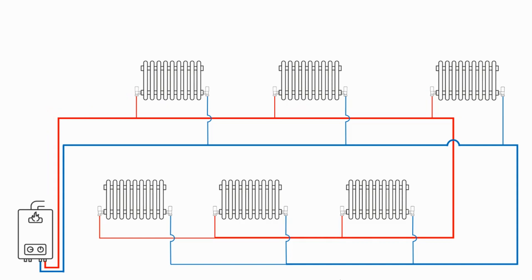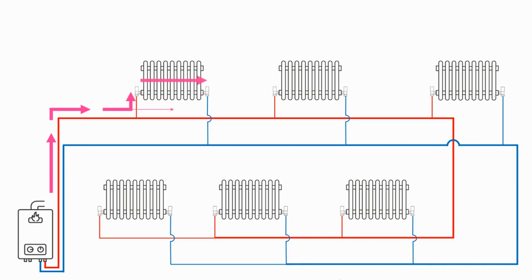Now here we have a scenario where the system is out of balance. This first radiator hasn't been balanced so the valves are wide open. As the hot water leaves the boiler and approaches the T it now finds that the path of least resistance is to go through the radiator and therefore it doesn't allow the water to flow on to the rest of the radiators on the system.